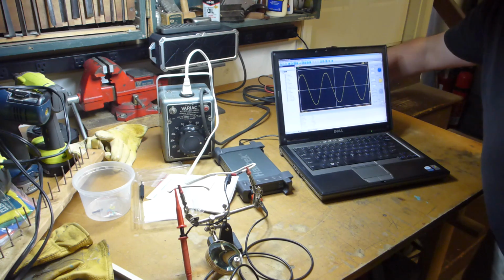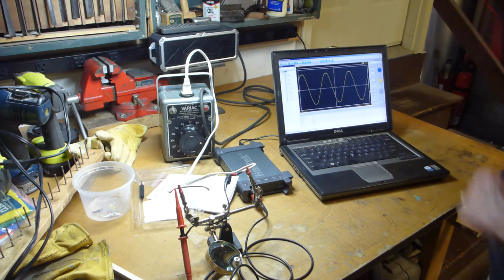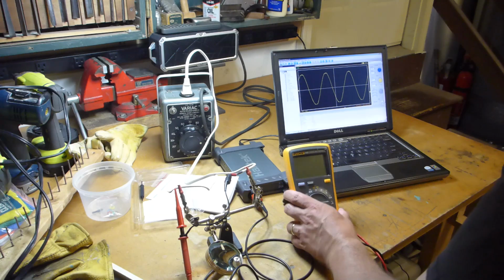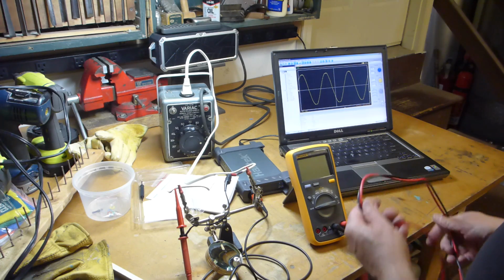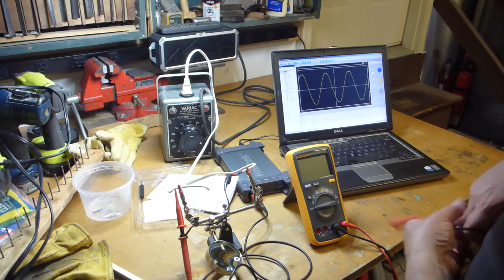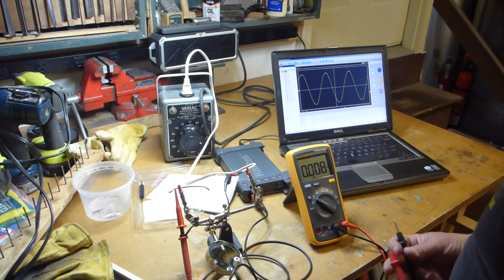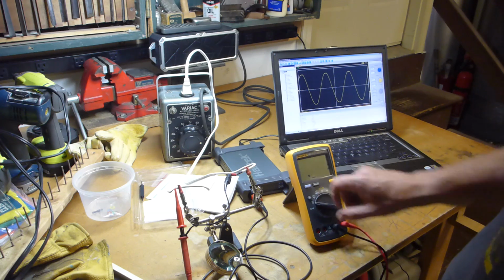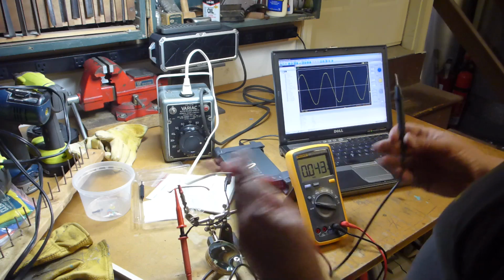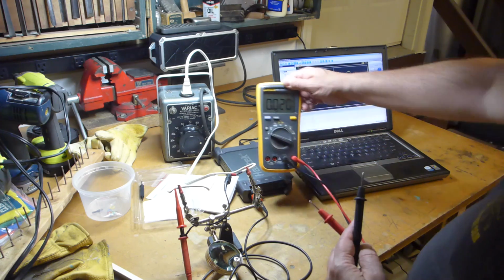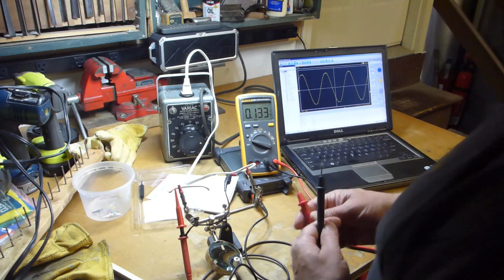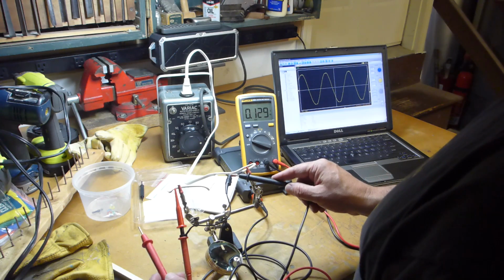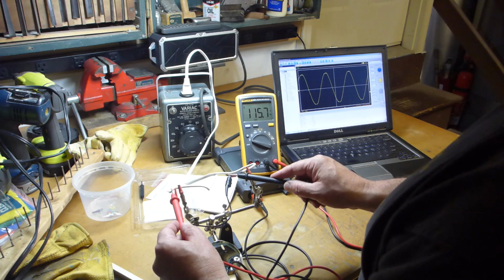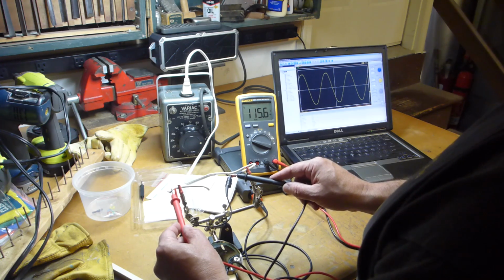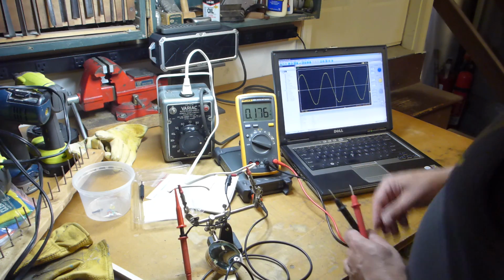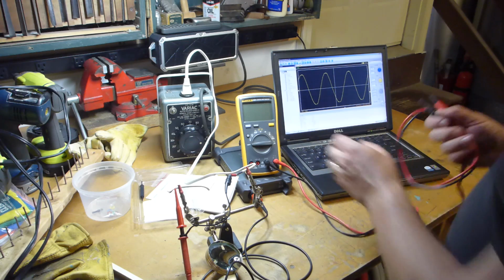And also, something I showed may have been lost to the battery gods is that I am getting a difference in RMS reading versus my standard Fluke reading for the voltage. My RMS says it's right in between 110 and 111 right now. Yet when I try my Fluke, which is not corrected, it's not a true RMS reader, I am getting 115.7. So there's a fairly substantial difference there.